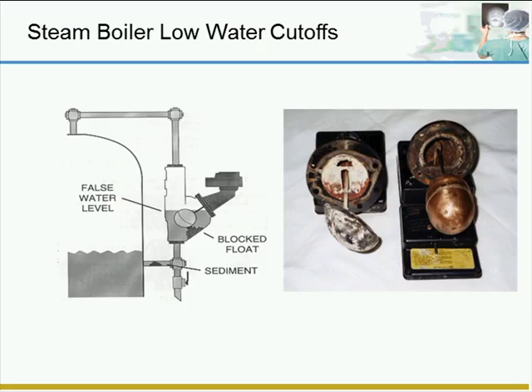All boilers have a low water cutoff. The boiler's low water cutoff will be located at the proper operating level for the water. The low water cutoff will shut down the boiler prior to the water level dropping below the lowest permissible water level. That is the main objective of the low water cutoff.